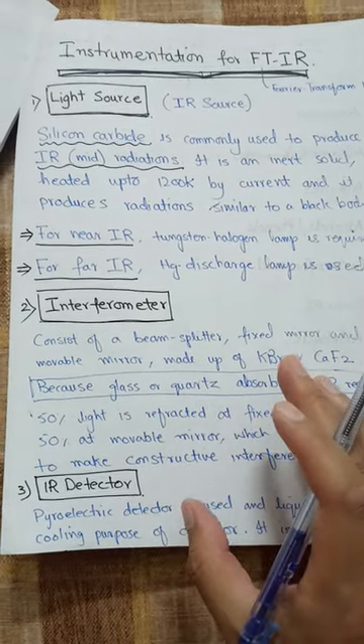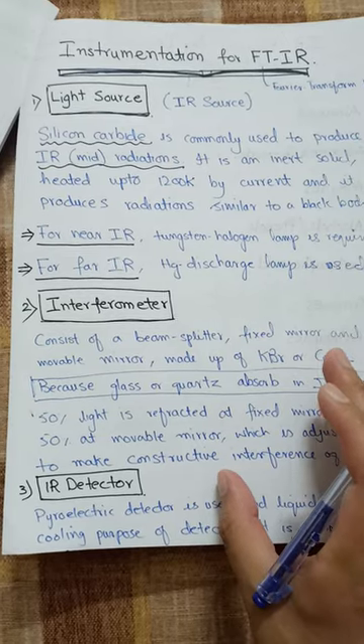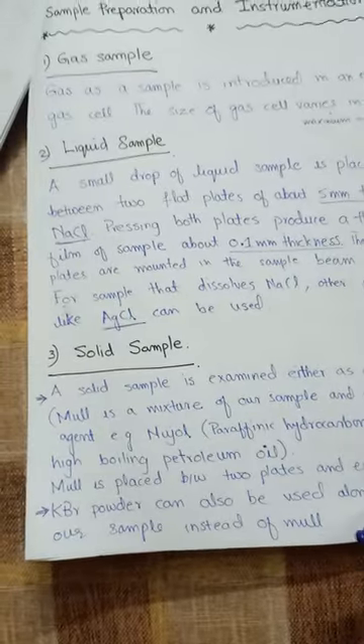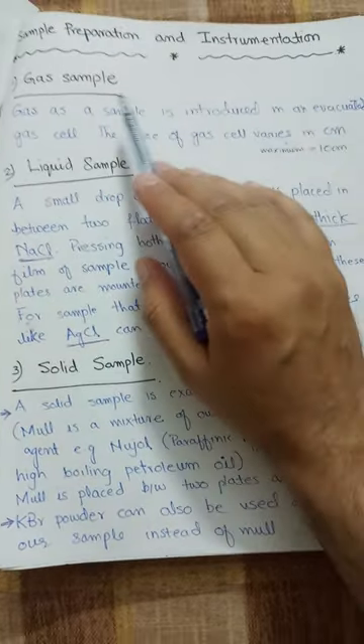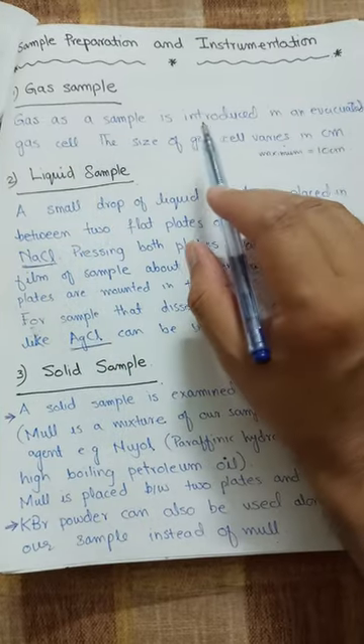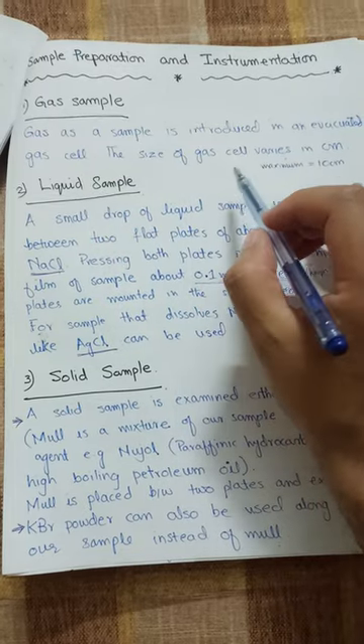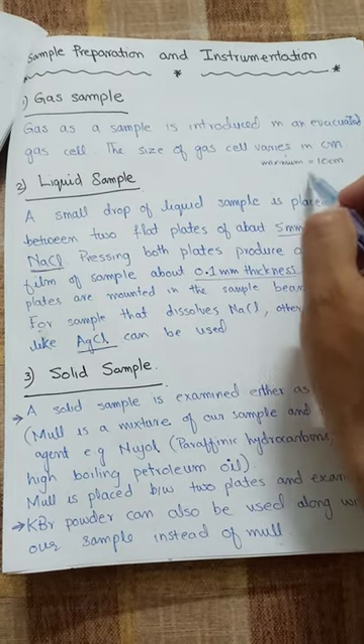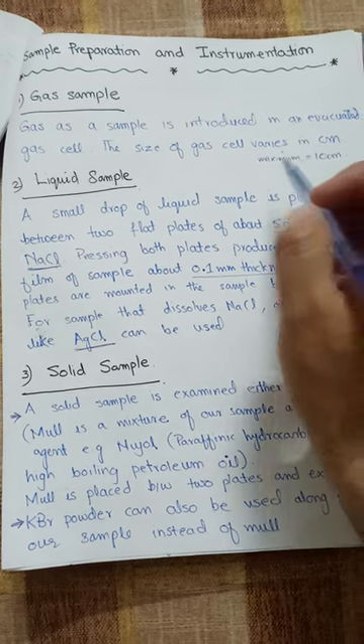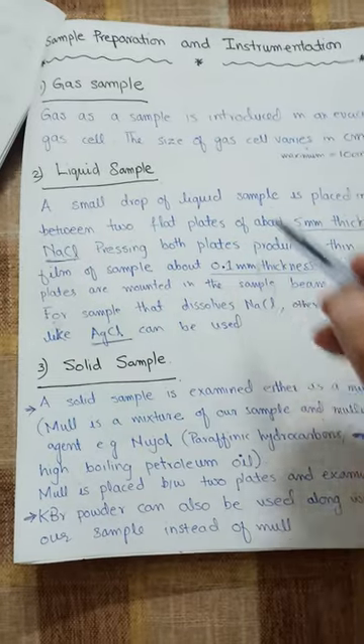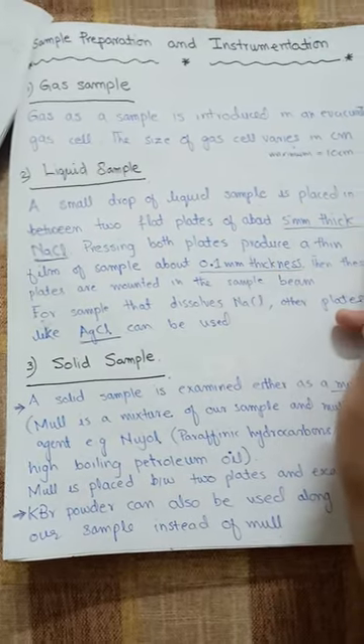Then this IR radiation falls on the sample in the sample cell, where the radiations are absorbed. The sample cell may be a gas sample, liquid sample, or solid sample. If we have a gas sample, it is introduced into an evacuated gas cell. The size of the gas cell varies — it can be from 1 centimeter to 10 centimeters.